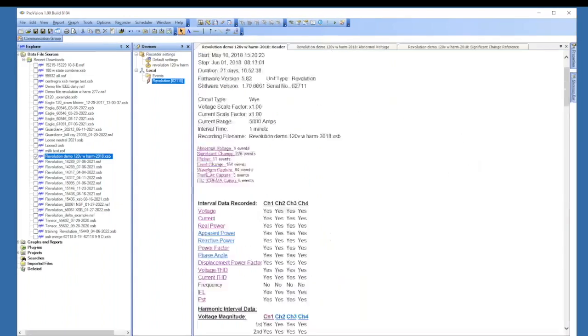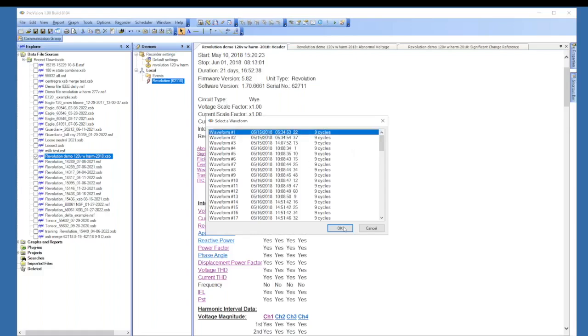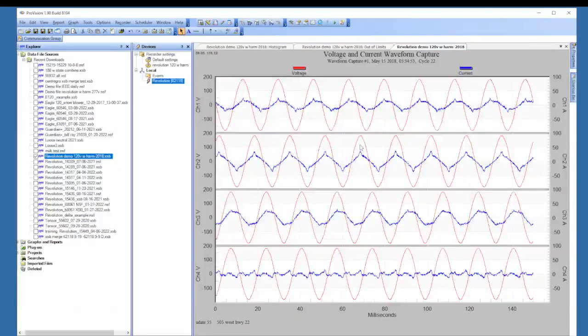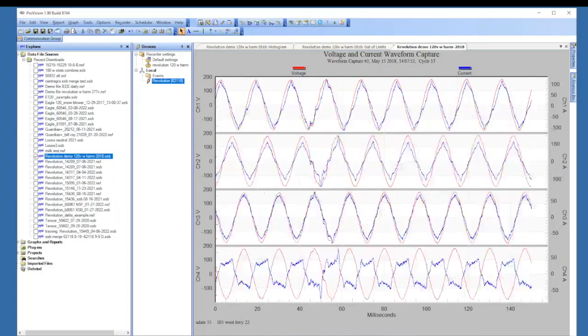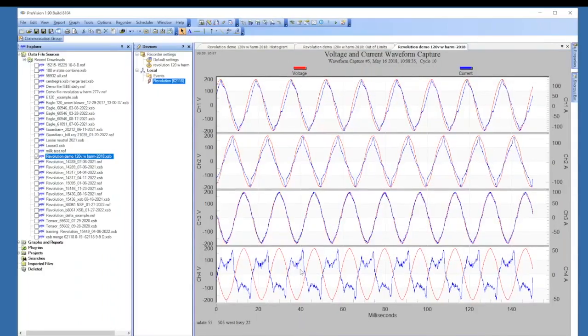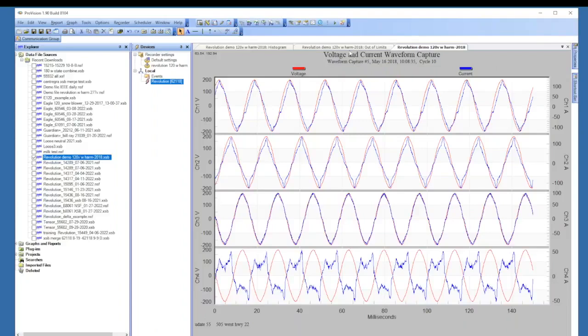a motor turned off. Waveform captures. You can click on a waveform capture, and again, you should see whatever your setting was. So normally 9 cycles. This is the trigger cycle. So when you see a date and time, this is the 3rd cycle. So this would occur in this area. You can page down and page up through these. And down on the bottom, you can see that this was flipped around. So if you have your Flexi T on backwards, and if this was neutral, this would be normal for neutral, but you wouldn't see that much voltage on there. But your waveform captures can also tell you if your Flexi Ts are flipped around also. I'll come back to waveform captures in a bit.